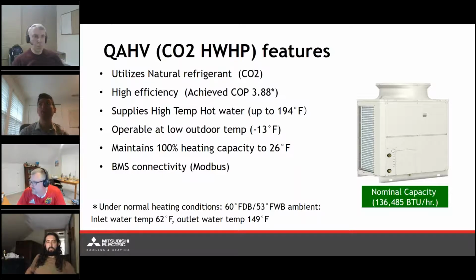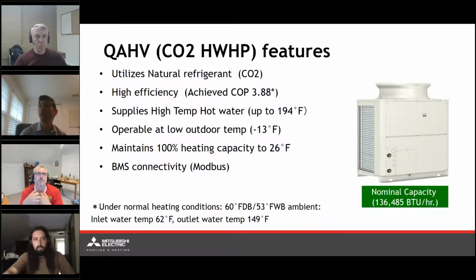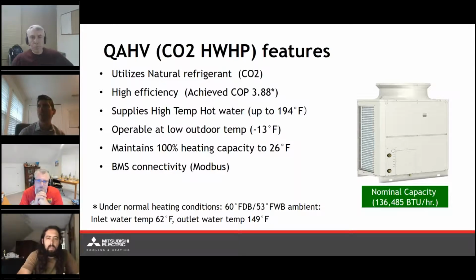And by utilizing CO2, we're able to get ultra high efficiency even at cold temperatures. So we're looking at just under a 4 in terms of the COP. And I believe I have those charts. Oh, that's right. I'm waiting on the derate charts to actually showcase how the COP is affected in low ambient conditions. But with that said, this particular unit can supply high temperature hot water up to 194 degrees. That is the European unit. We anticipate that when this goes through its certification and testing process in the United States, I'm unfamiliar with the guidelines for hot water equipment, but I believe ultimately that's going to be reduced down to about 185 degrees. But with that said, it's capable of producing hot water up to at least 194.